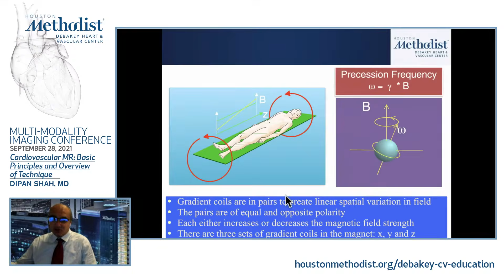And so the purpose of using these gradients is to do really three steps. One is to select a slice of interest. Two is to do something called phase encoding. And three is to do something called frequency encoding. And we'll go through this quickly. So the first step is I pick the slice that I'm interested in imaging. On the scanner, all you're doing is moving a mouse, and I can say either I want to image here in the chest, or I can move the slice up higher, image up in the head, or whatever location I'm interested in imaging.